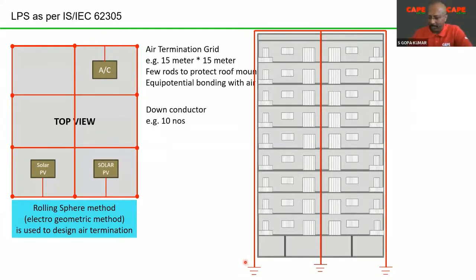What is an earth termination system? It consists of an earth electrode, because whatever current comes from the top due to a lightning strike through the down conductor has to be dissipated to soil. So there are 10 earth termination systems or 10 earth electrodes in this particular case. So you have the air termination, you have the down conductor, and you have the earthing.